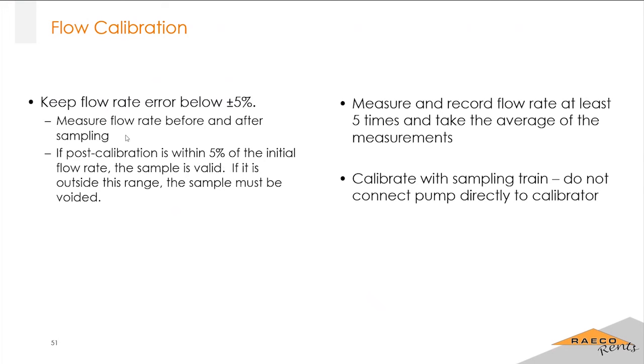Again, just those flow rates are really important, especially if you're using cyclones. You're not going to be getting the right cut point, which is essentially how these cyclones are separating out your particulates. If your flow rate's not good, your separation of the particles isn't good. So you want to make sure that that is as close as possible to the proper flow rate.